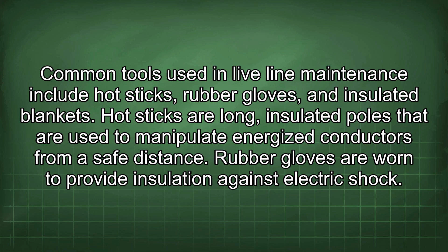Safe work practices are also essential for performing live line maintenance safely. These practices include maintaining a safe distance from energized conductors, using insulated tools and equipment, and wearing appropriate PPE. Workers should also be aware of the potential for arc flash and take steps to protect themselves from this hazard.